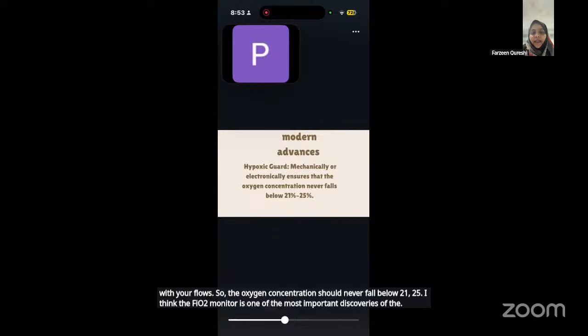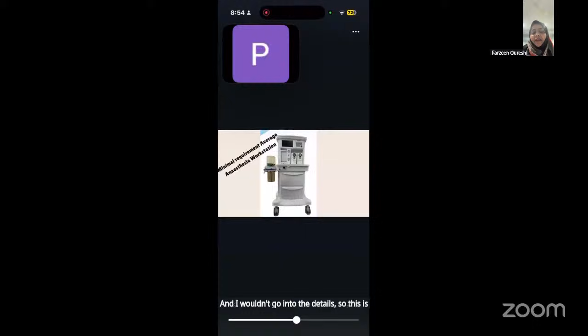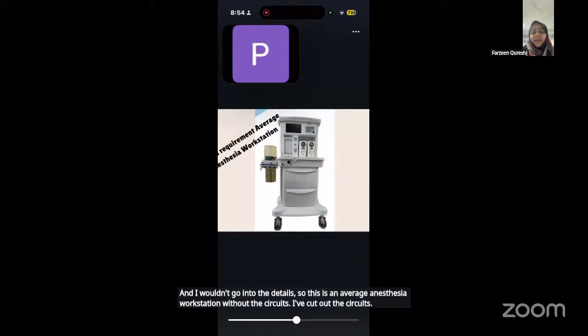So the market leaders, this is nothing to do with any personal choices, but the GE Healthcare, the Draeger, and the Mindray have got excellent models of the most modern anesthesia machines. And I wouldn't go into the details. So this is an average anesthesia workstation without the circuits. I've cut out the circuits and the filters so that it looks basic. So here you can see it is nothing but your Boyle's machine with the advanced vaporizers and a ventilator with a soda lime for the circle system absorption.